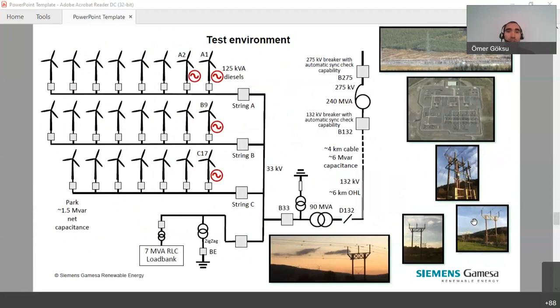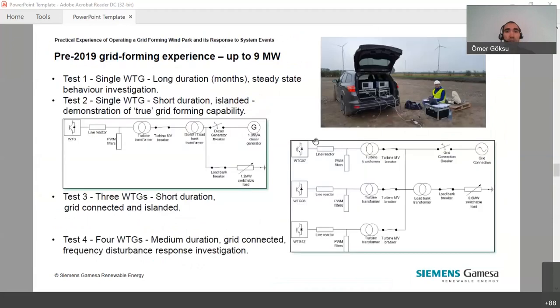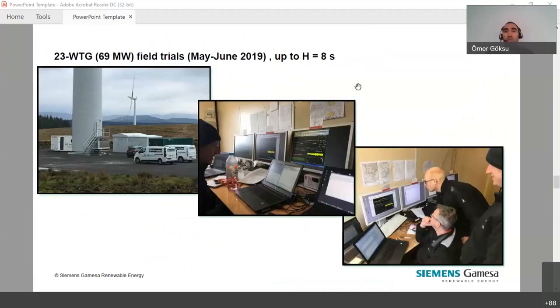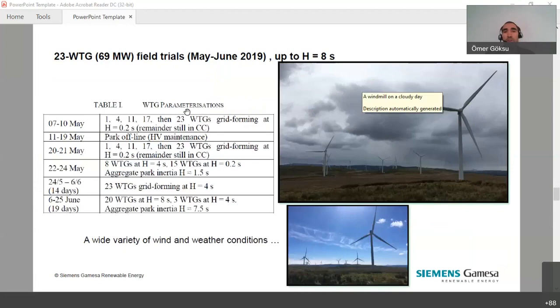In 2019, the test was expanded to a wind farm in Scotland with 23 turbines, 3 megawatts each. The topology might be different in the different test cases, but I just wanted to show the wind farm first. It started in May, June 2019, and the inertia constant for the wind farm was up to 8 seconds. Various scenarios were tested, with some turbines in grid forming mode, some in grid following mode, current control, and different inertia constants from 0.2 seconds up to 8 seconds.